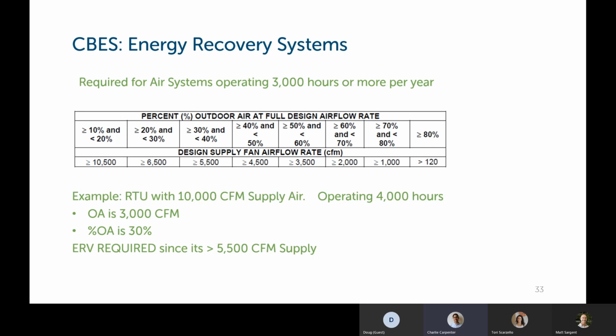And then you would just go down the table there to show what the design supply airflow rate would be or must be in order to need an energy recovery system. And that states greater than or equal to 5,500 CFM. And as I note here, this is a 10,000 CFM supply unit, which is greater than 5,500. So based on all that, this rooftop unit would need energy recovery serving it. So hopefully that makes a little bit more sense how to look at the table.